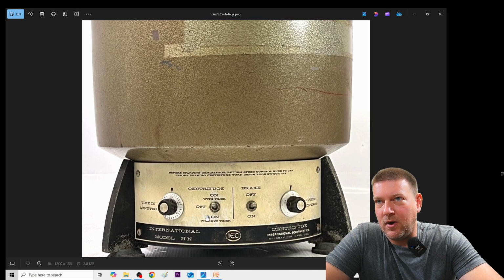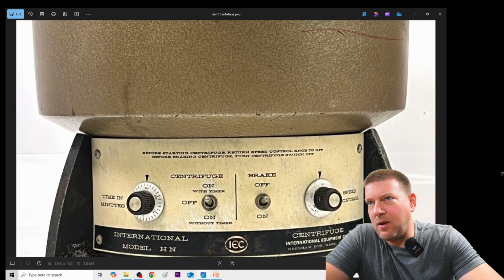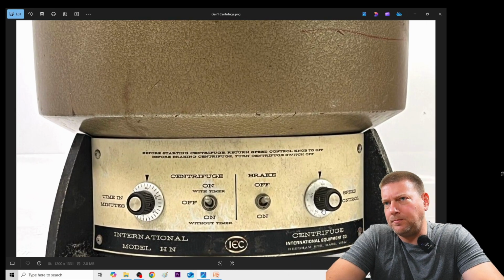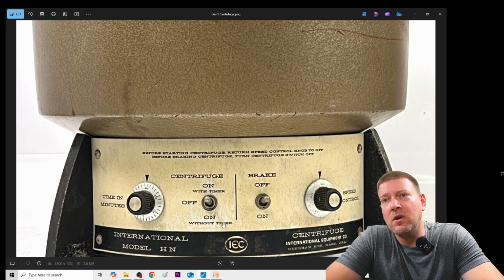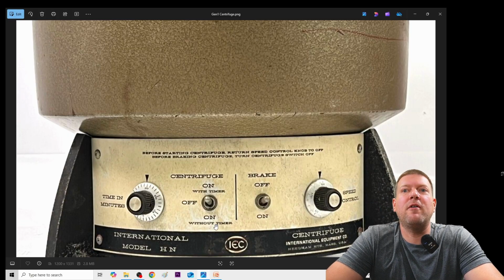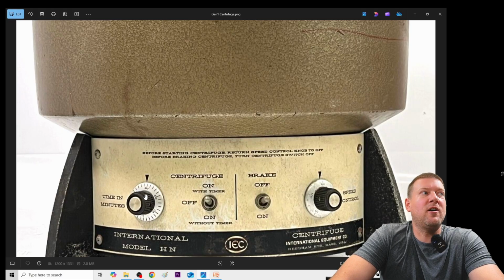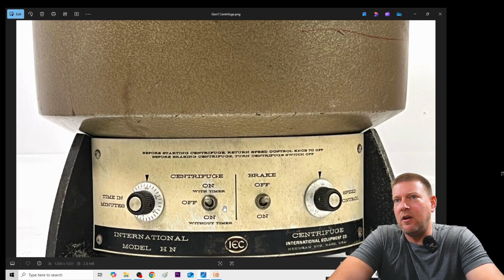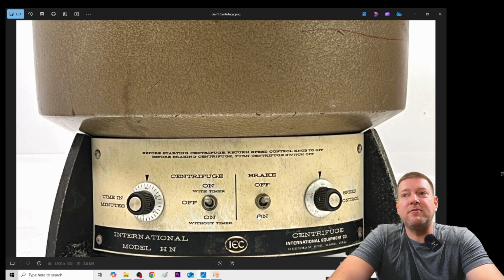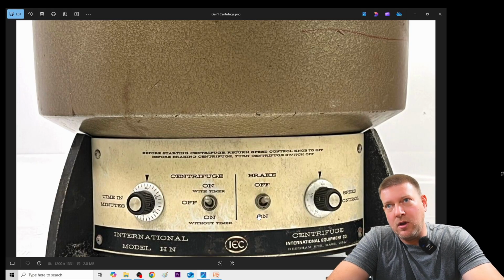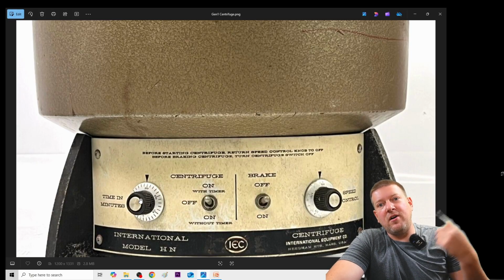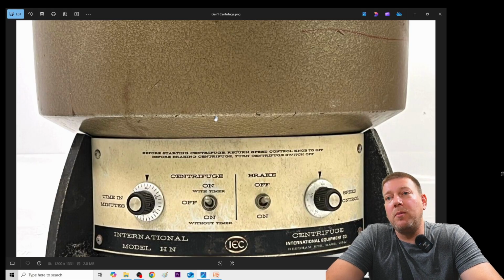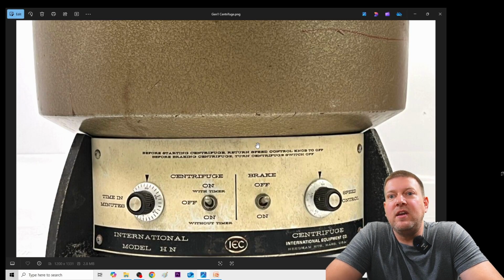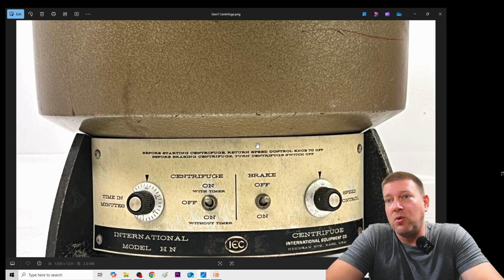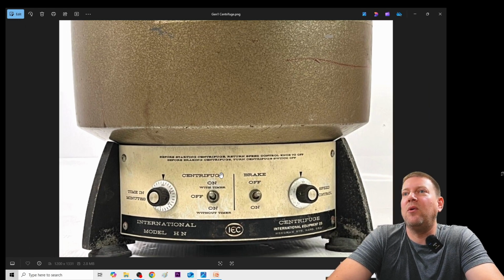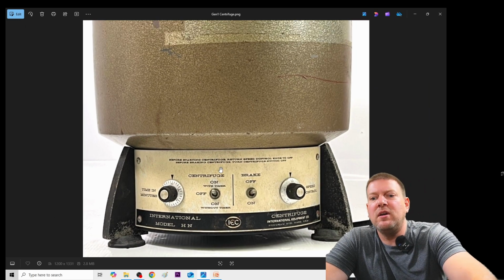Oh, here's a good one. So we have a timer and we have a speed control. If this one's a speed control, a Variac, I would assume, and on with timer, off without timer. So it's basically just running it off of this one or this one over here, and brake on and off. So it does have a braking resistor, which means when the timer runs out, it will absorb the extra energy, and the induction in the coils of the motor will create a motor brake. Man, that's an oldie but goodie. I've actually seen this centrifuge in person.